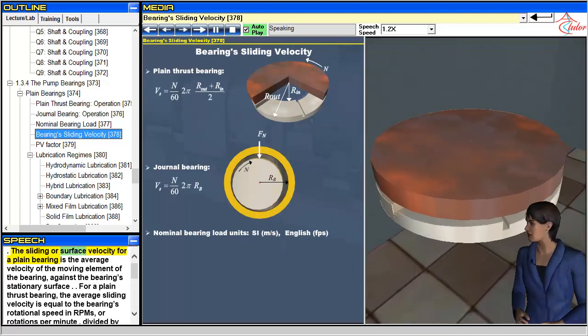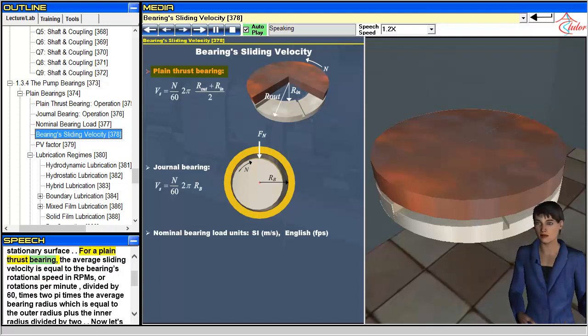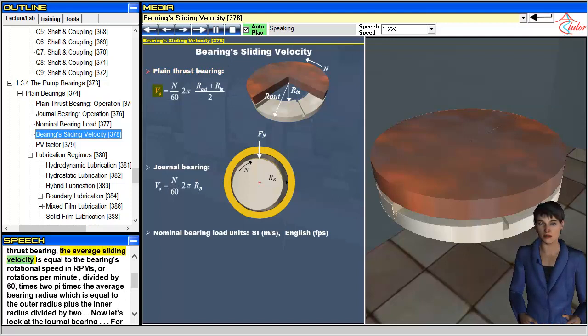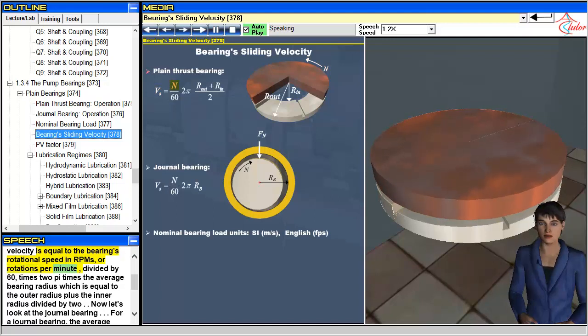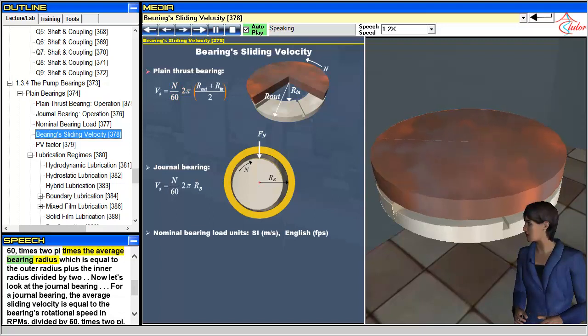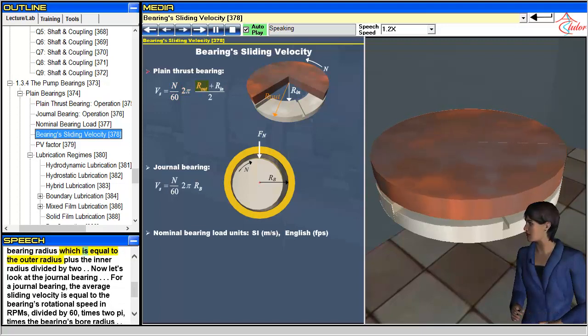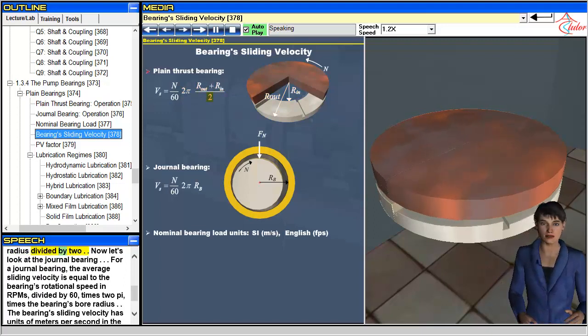The sliding or surface velocity for a plain bearing is the average velocity of the moving element of the bearing against the bearing's stationary surface. For a plain thrust bearing, the average sliding velocity is equal to the bearing's rotational speed in RPM divided by 60, times 2π, times the average bearing radius, which equals the outer radius plus the inner radius divided by 2.